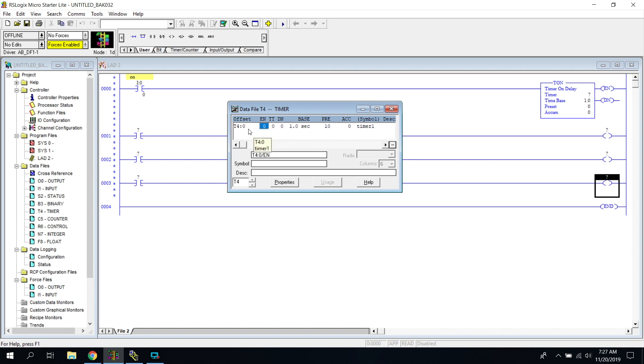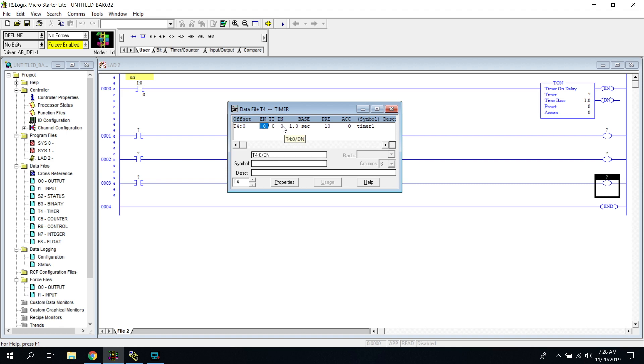The preset and accumulation bits we'll play with later in math instructions. For right now we're going to focus on these three output bits. What they do is become true at different times based on what the timer does. The timer enable bit will come on when the timer is true and will stay on as long as the rung is true. The timer timing bit will be on for the duration the timer is timing — so if you set up the timer for five seconds, it will be on for five seconds. The timer done bit will come on when the timer is done.